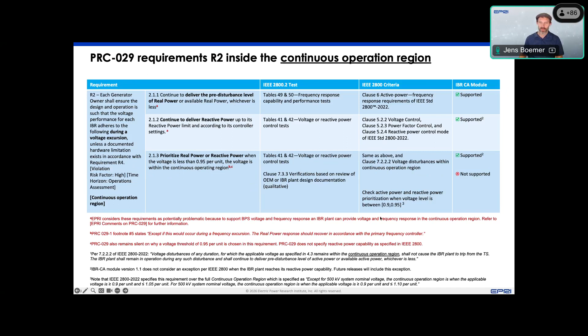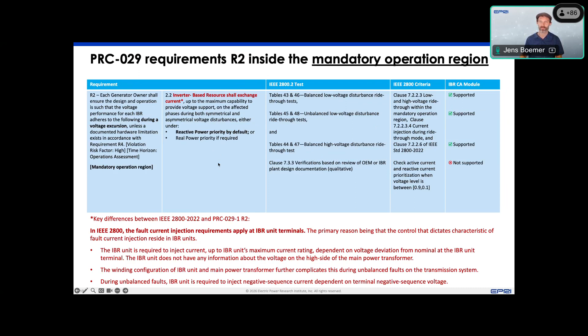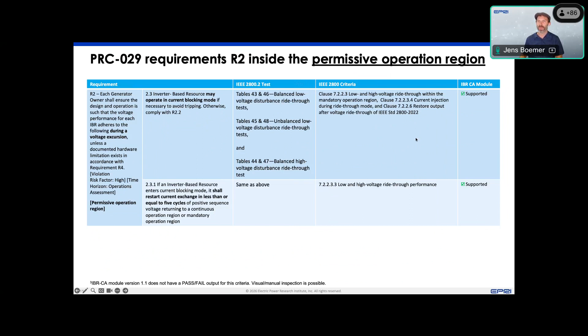Now, for the mandatory operation region, it's important to highlight that the PRC 29 standard requires the inverter-based resource to exchange current in a certain manner, whereas IEEE 2800 requires the IBR unit to inject reactive current in addition to the pre-fault current, both in negative and positive sequence. So IEEE 2800 is very detailed in that regard, and all of these details can be assessed with IEEE 2800.2 tests and the EPRI IBR conformity module. For the permissive operation region, which is the region where it is allowed for the IBR plant to enter momentary cessation or current blocking, those criteria are also specified in the IEEE 2800 context, and the EPRI conformity assessment module can assess all of those.